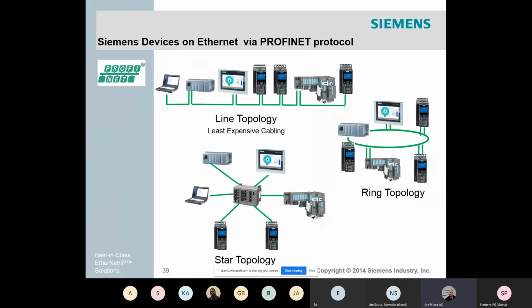Fieldbus was invented to reduce the amount of wiring. Big, large cable runs back to the main PLC. Line topology is less expensive. No need for performance; the customer is only worried about the amount of wiring costs. With the Siemens products, with the 2-port switches built into all of our products, we can create a line topology without the additional cost of a switch.